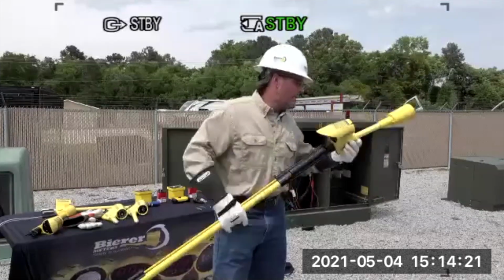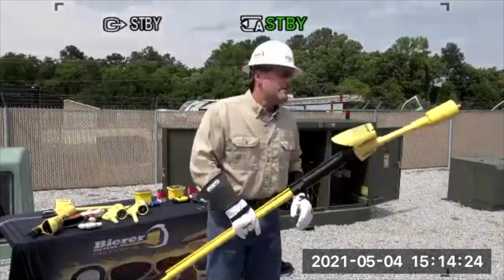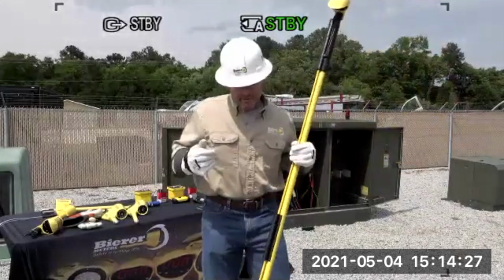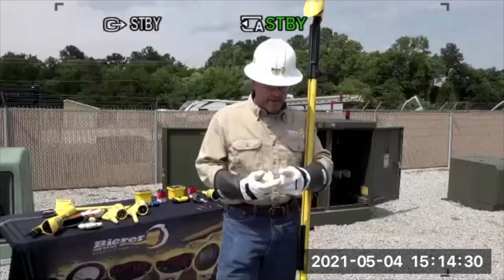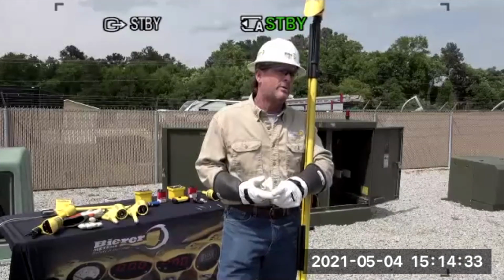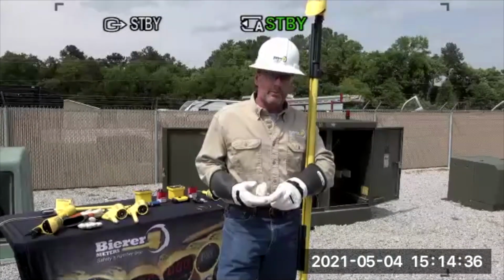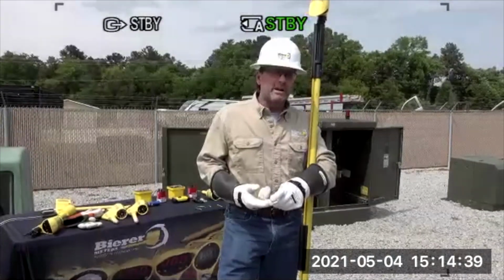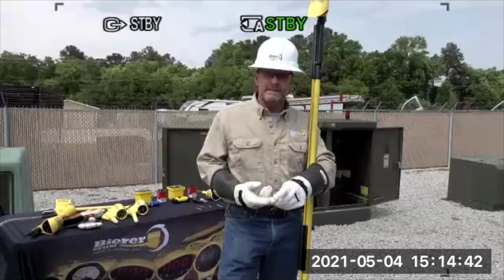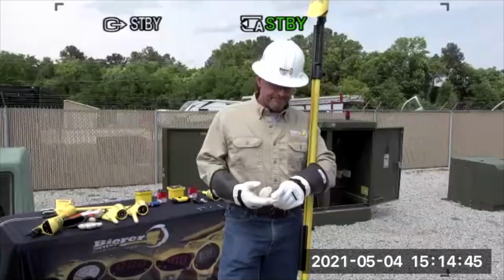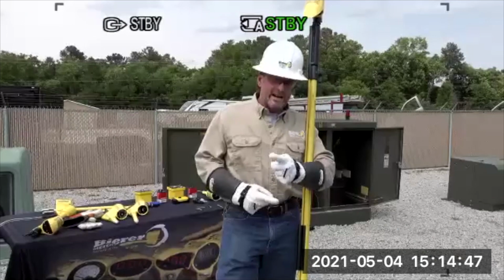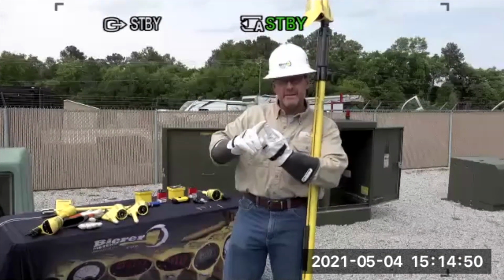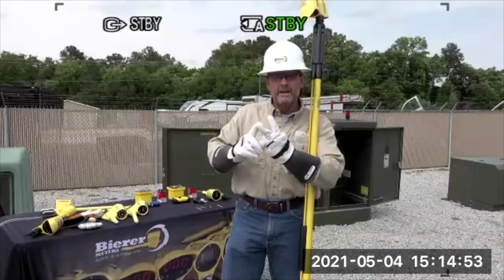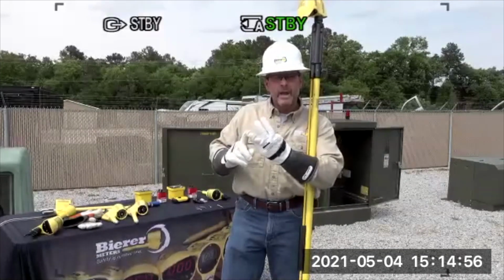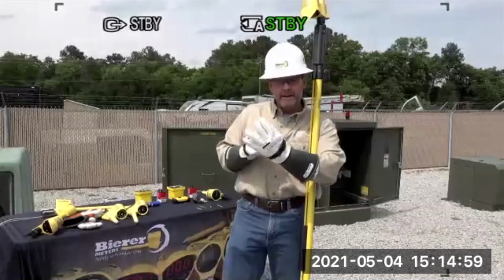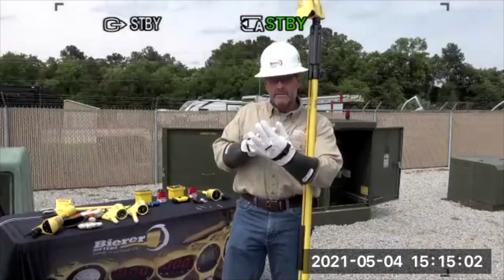So what we're going to do now is, prior to checking dead, we're taught to verify there's a lack of nominal voltage. We're going to look for a lack of all three, as we previously said, and then we're going to put on our grounds, our TPGs. So we're going to do a couple things differently. We're actually going to do a live test. We're going to test, then open, then test, then test our tester, then place our grounds.